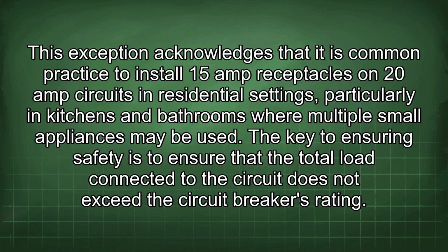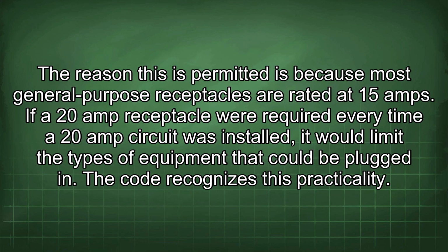This exception acknowledges that it is common practice to install 15-amp receptacles on 20-amp circuits in residential settings, particularly in kitchens and bathrooms where multiple small appliances may be used. The key to ensuring safety is to ensure that the total load connected to the circuit does not exceed the circuit breaker's rating. The reason this is permitted is because most general-purpose receptacles are rated at 15 amps. If a 20-amp receptacle were required every time a 20-amp circuit was installed, it would limit the types of equipment that could be plugged in. The code recognizes this practicality.